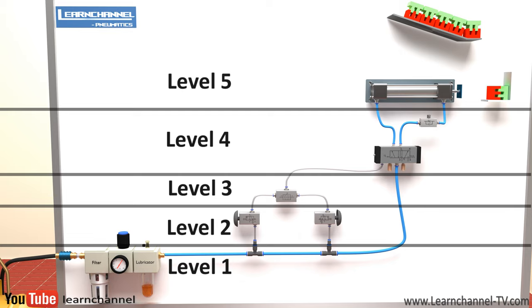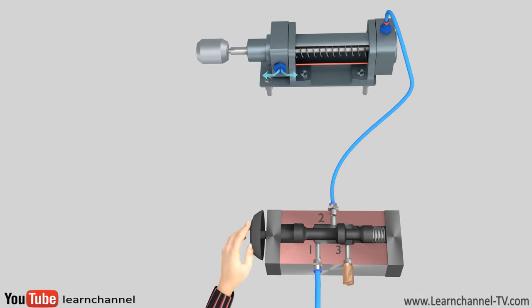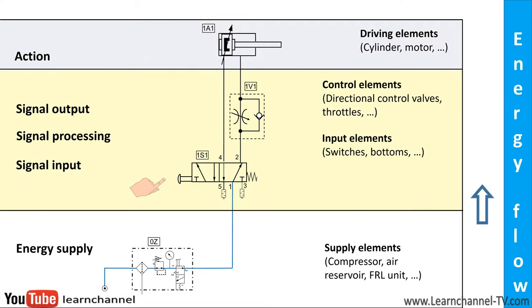Here you get the associated circuit diagram with its different levels. Note that the energy flow in the pneumatic circuit diagram runs from bottom to top, starting with the compressor and FRL unit and ending at the actuator. But note, within simple circuits, a pneumatic component may provide the function of multiple levels. Here, this manually operated 5/2 valve acts as an input element and final control element at the same time.